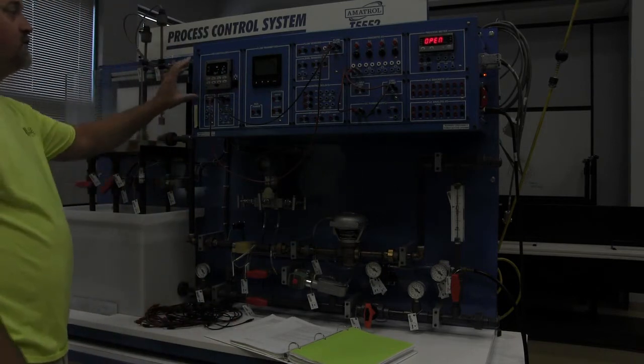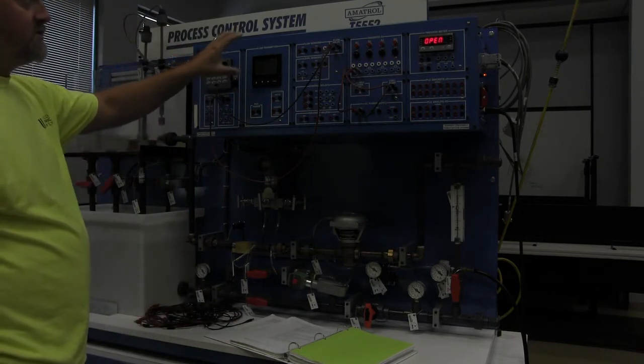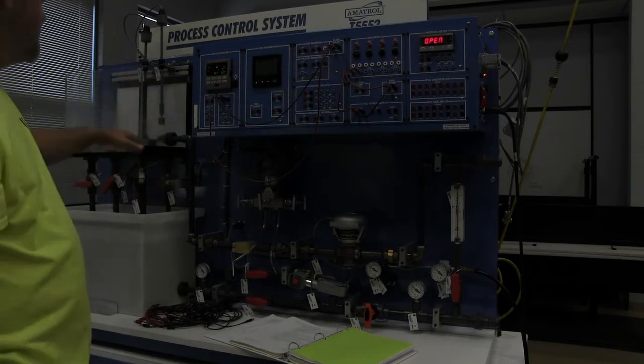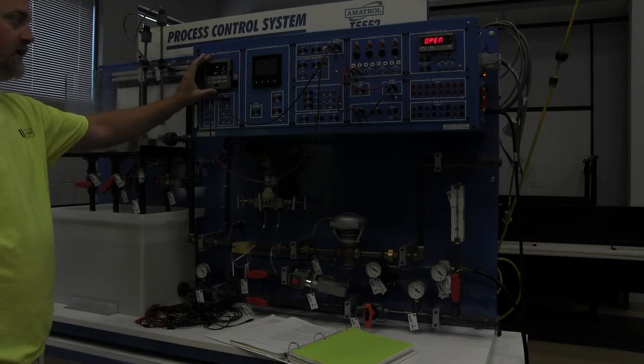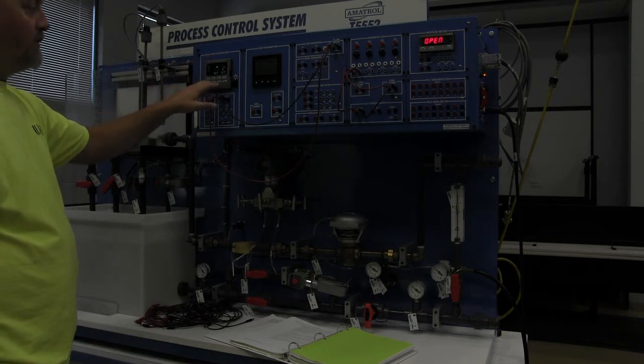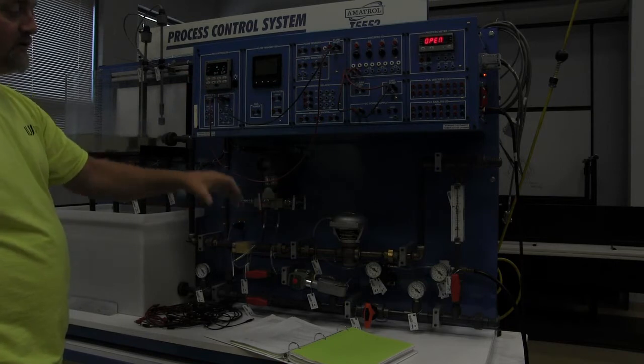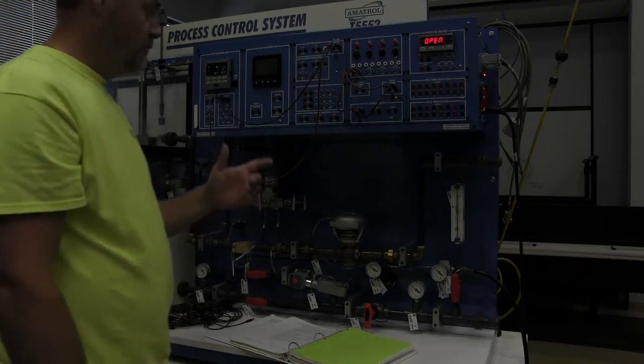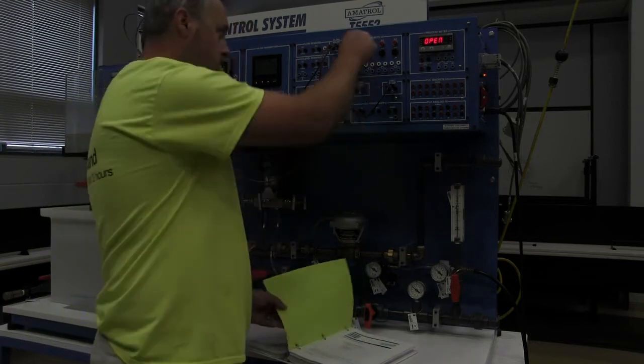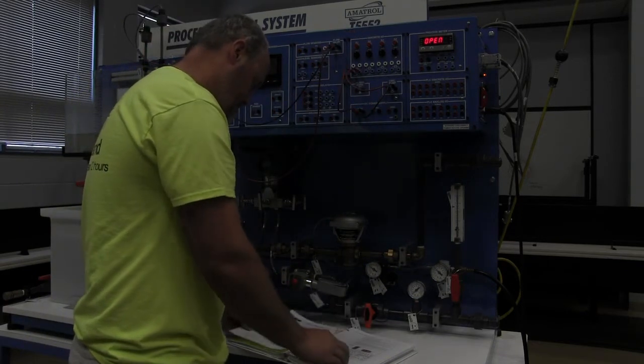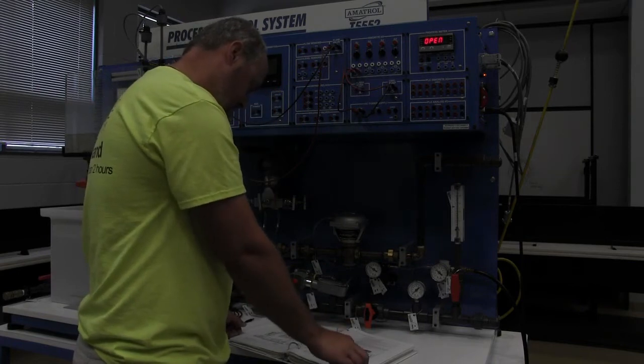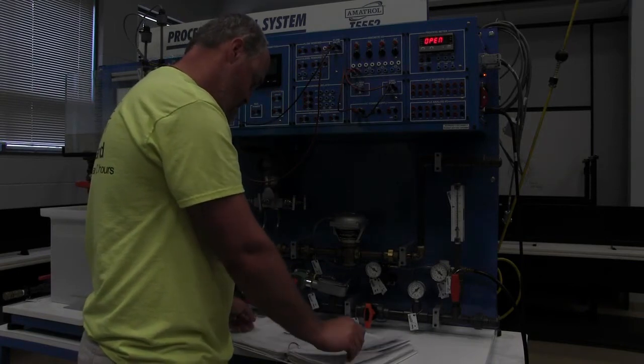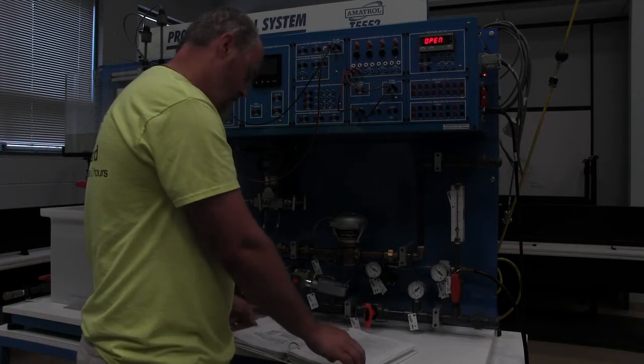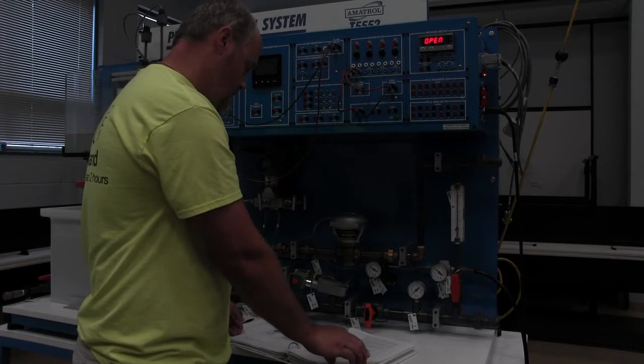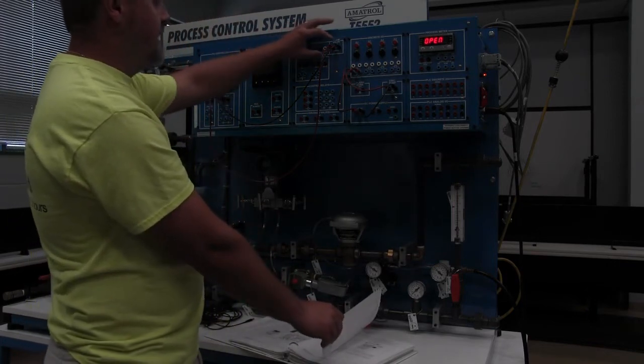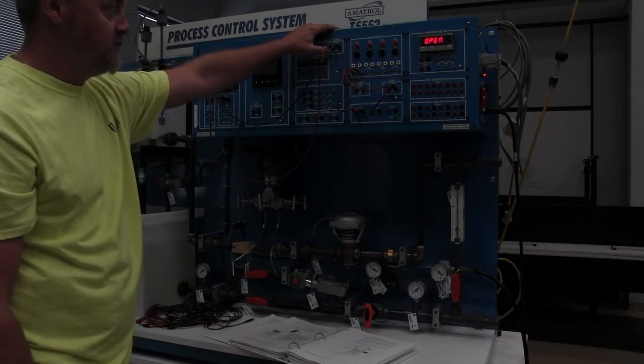So that is just a way of using an analog output from this device to a flow control to maintain a level. But currently we're using it in a manual mode. So as we need water, we have to increase or decrease to open or close the valve to put more water in the tank. Soon we'll be doing it automatically. So basically what we're doing is increasing and decreasing the analog signal. And in this instance, the analog signal is a 4 to 20 milliamp.